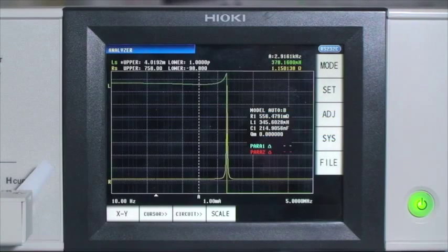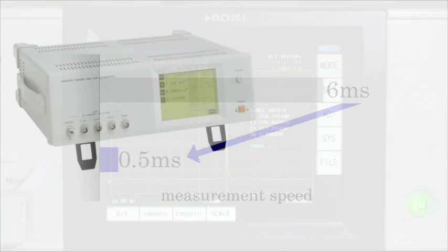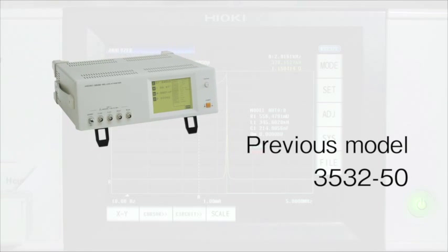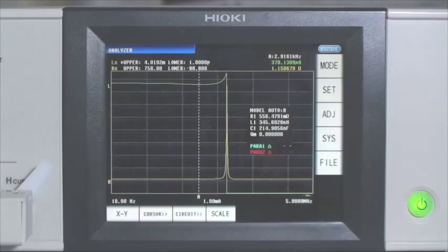The IM3570 has increased the speed at which measurements are taken by 12 times from 6 milliseconds to 0.5 milliseconds over previous models at 1 megahertz without losing any accuracy. In fact, the accuracy is better than the 3532-50 LCR meter.